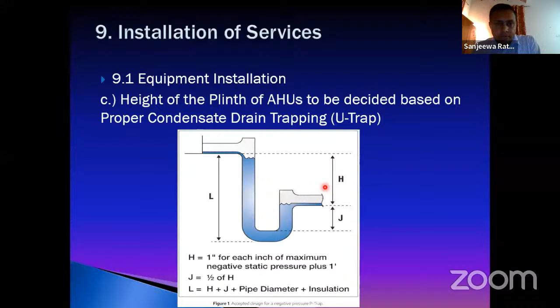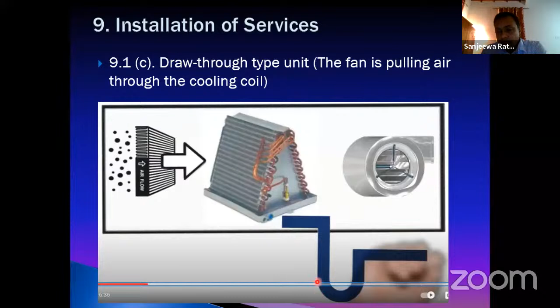You can see this is a draw-through type fan coil unit, where the blower is after the coil. So we call it the draw-through type. The airflow is drawn through this coil. In this case, we have put this U-trap because condensation forms on this coil. So there is negative pressure inside this coil, so this height L should be a bigger value.